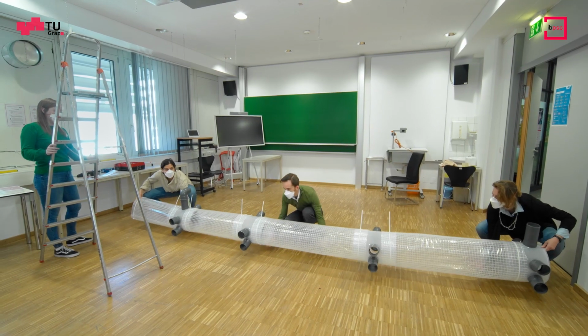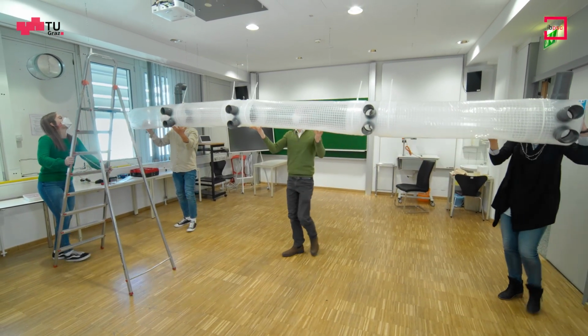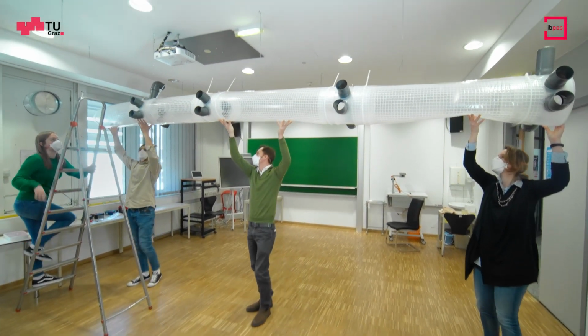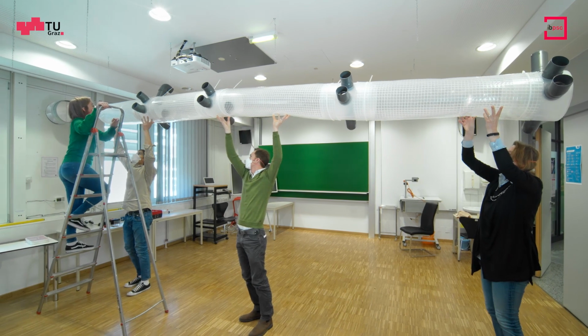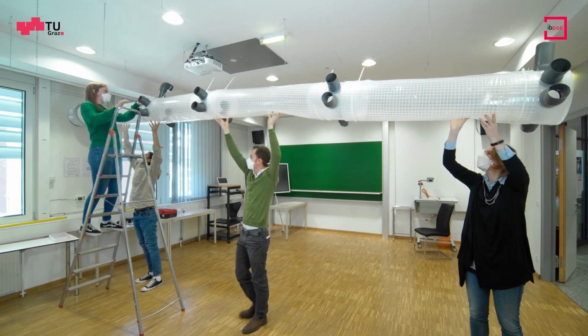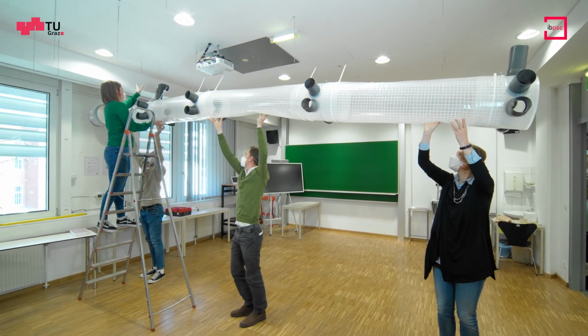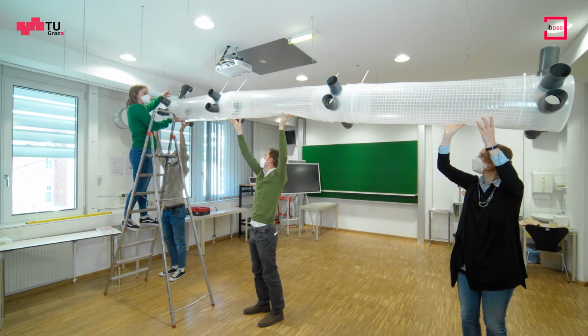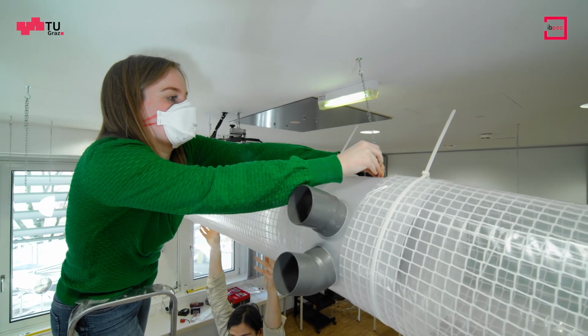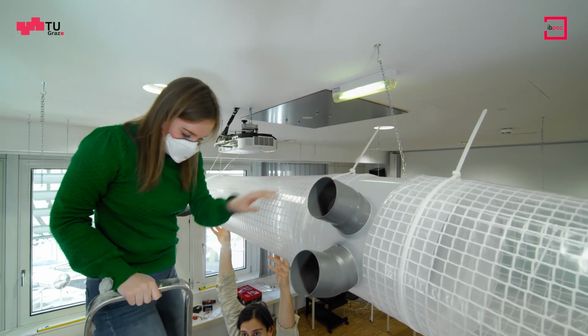The chain can be fixed to a ring hook fixed to the main duct, or if greater security is desired, a wire hanging loop can be created using copper wire wrapped around the duct. Once the fixing hooks are in position, the chain is attached to the main duct and it can be lifted into place. Although it is very light, it is good to have a number of spare hands available to assist with the lifting into position so that it can be raised and held level whilst being fixed in place.